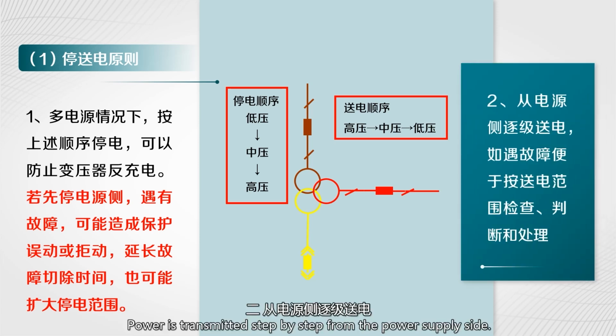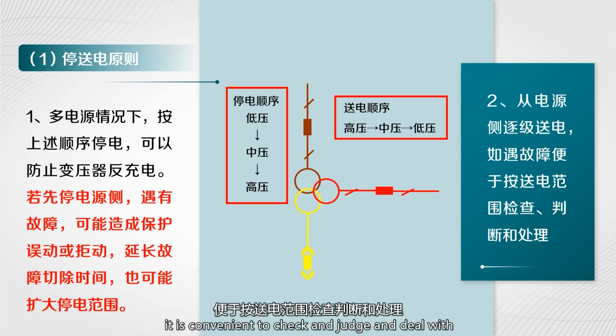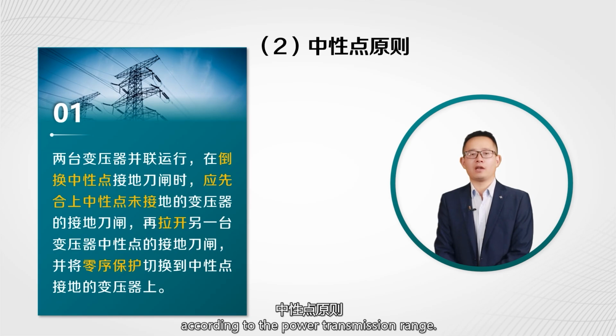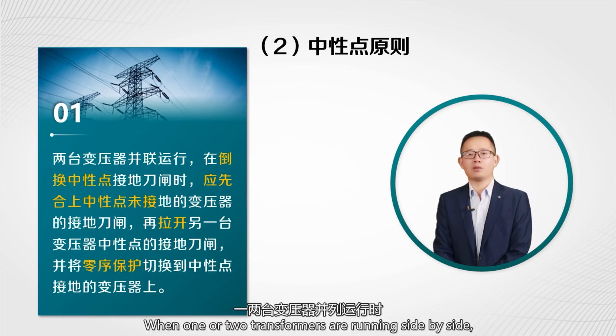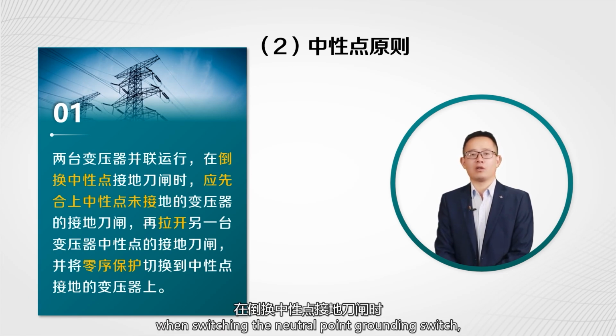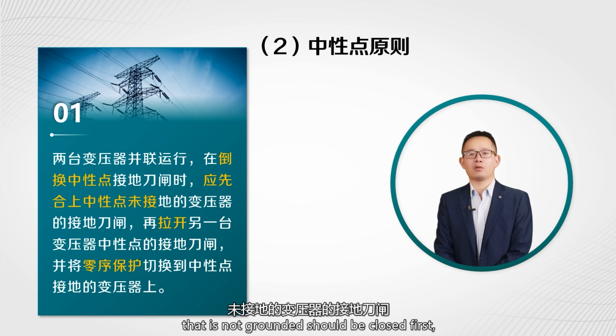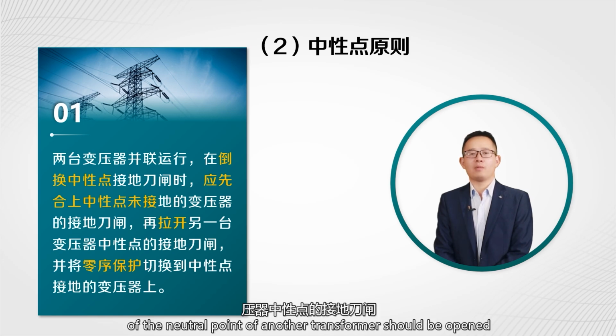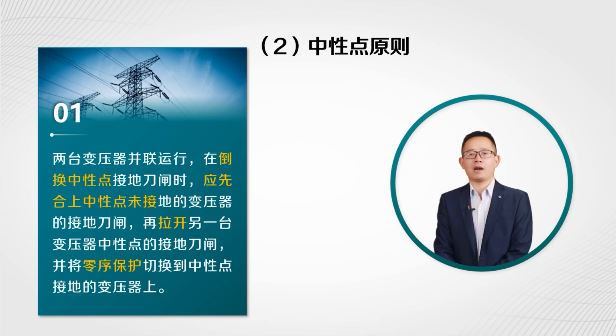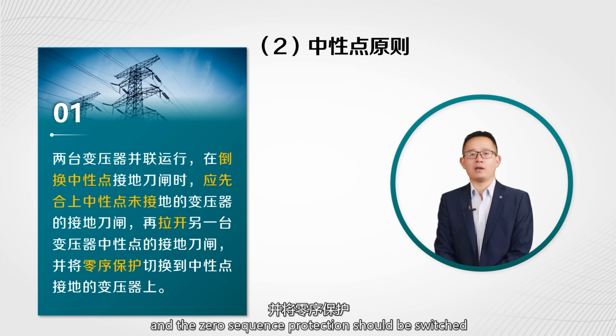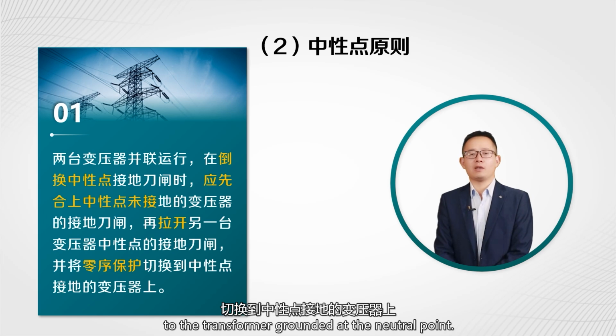Power is transmitted step by step from the power supply side. In case of failure, it is convenient to check, judge and deal with it according to the power transmission range. The neutral point principle: when two transformers are running in parallel, when switching the neutral point grounding switch, the neutral point grounding switch of the transformer that is not grounded should be closed first, and then the grounding switch of the neutral point of the other transformer should be opened, and the zero sequence protection should be switched to the transformer grounded at the neutral point.